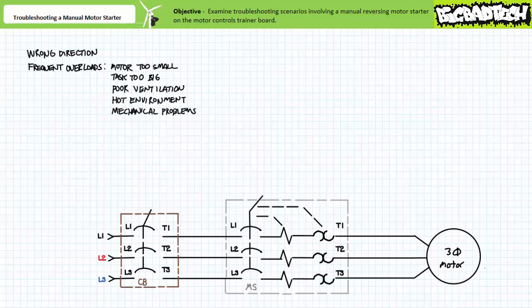If a 200-watt motor is assigned a 300-watt task, the manual motor starter will overload. If a motor receives insufficient ventilation, the manual motor starter will overload. If the motor is covered in a thick coating of sawdust, the manual motor starter will overload. If the motor is regularly locked in a black box on the roof of a metal smelter mid-summer, the motor will overload. Long story short, if you are regularly using a motor improperly, the manual motor starter will regularly overload.